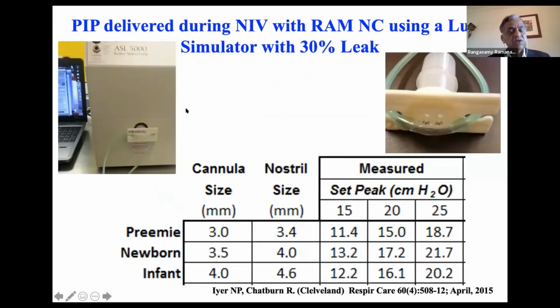The other question people always ask: how do you know if you are transmitting the pressure? Here is a study published by one of the neonatologists, Prabhu Iyer from Cleveland, and a respiratory practitioner. They took a test lung. This is a computerized test lung that's validated to do measurements. They created a 30% leak at the interface and then used the 3 sizes, preemie, newborn, and infant. Cannula size, this is the nostril size, and this is the measured peak pressure. If we set 20 centimeters, you deliver about 70% of the PIP at the hypopharyngeal level. If you use the newborn size, you transmit 80%. If you do infant, you generate close to 80 to 90% of the PIP.